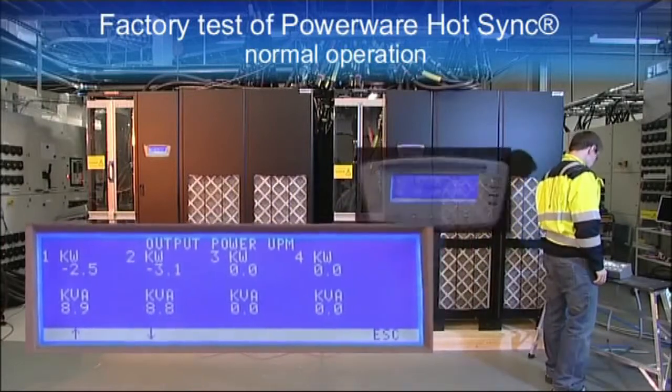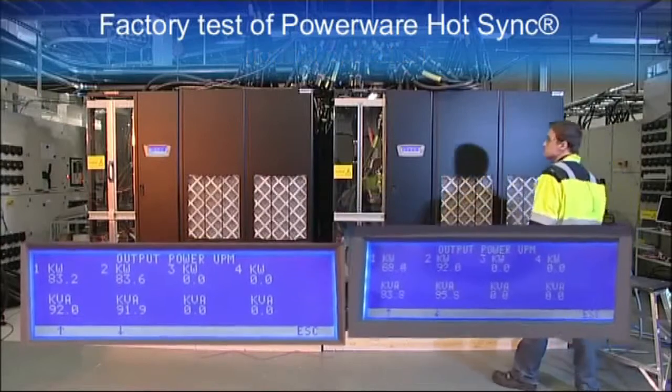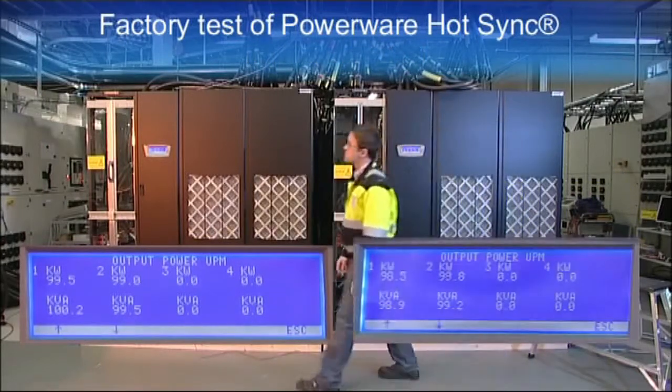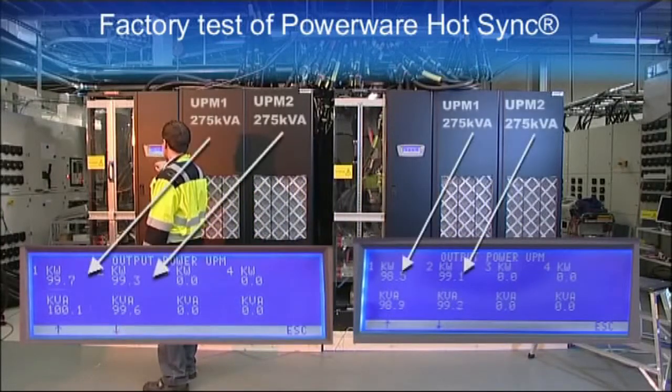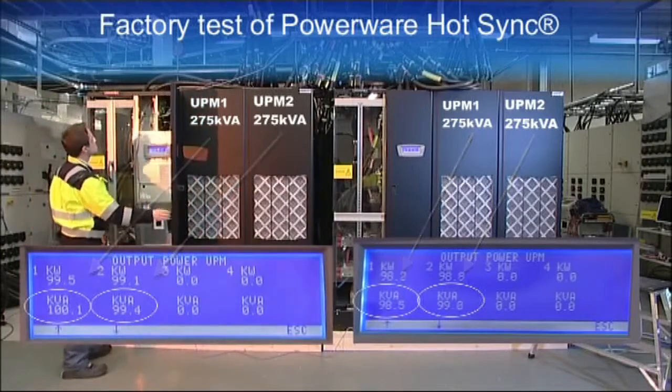We increase the load and see that the load is shared equally. There is a communication line between the units. Communication is not used for load sharing, but to convey information and alarm signals in the system.